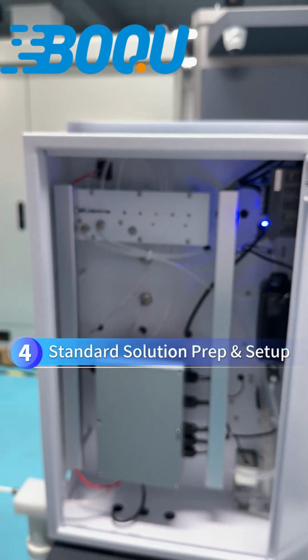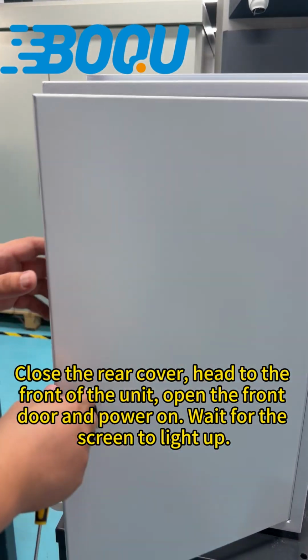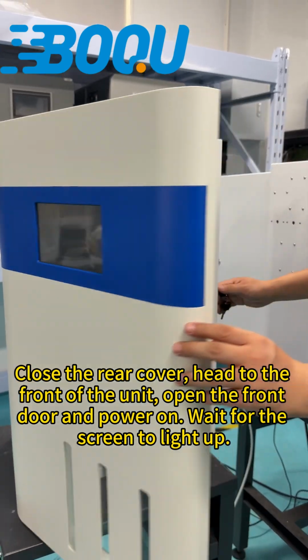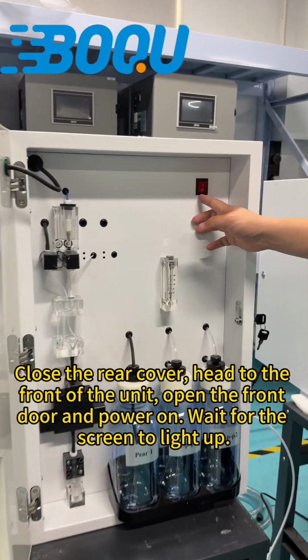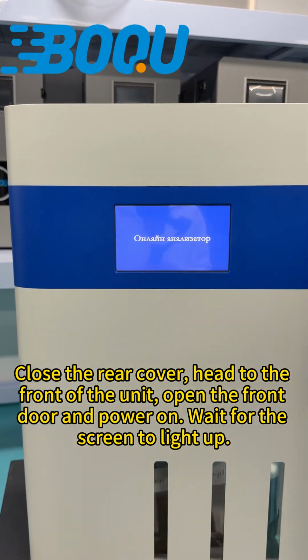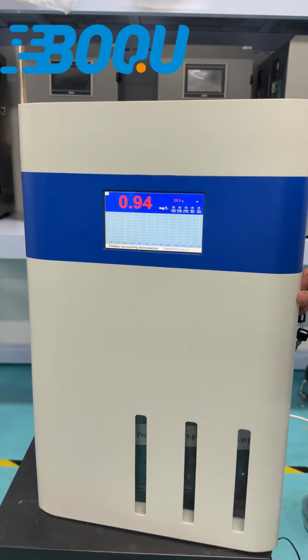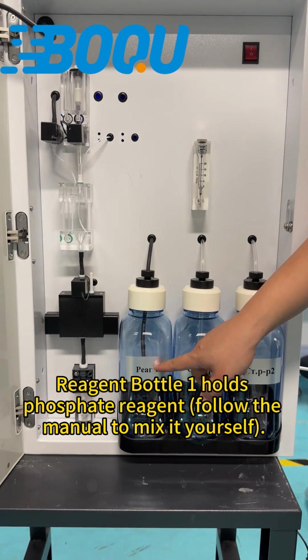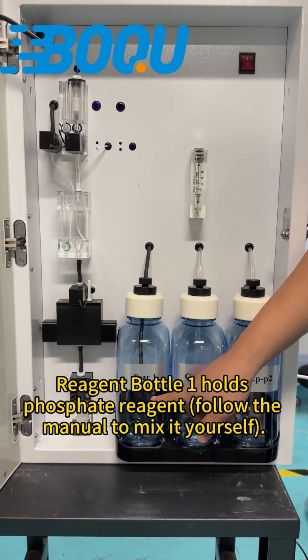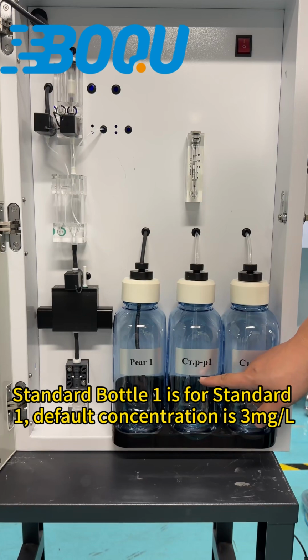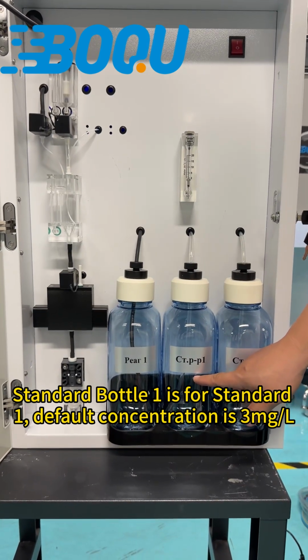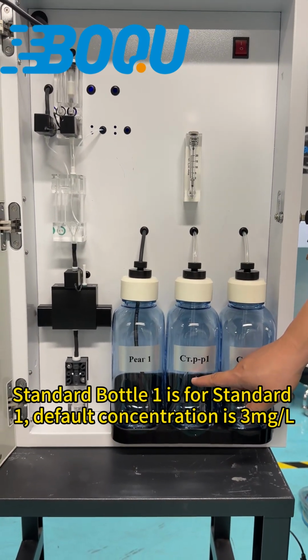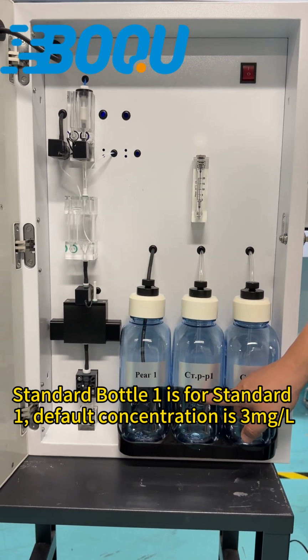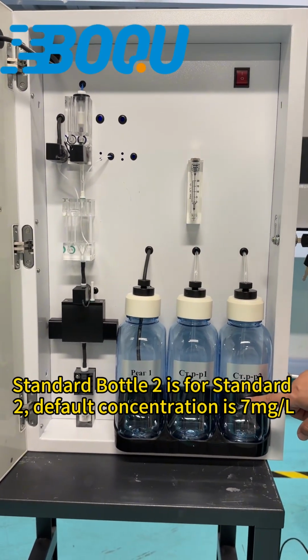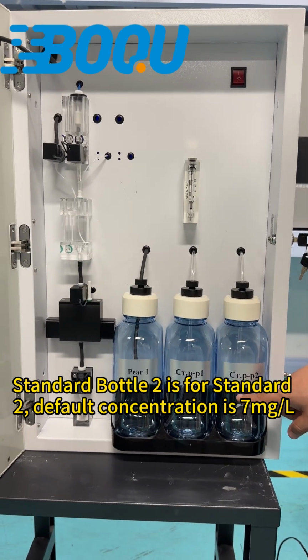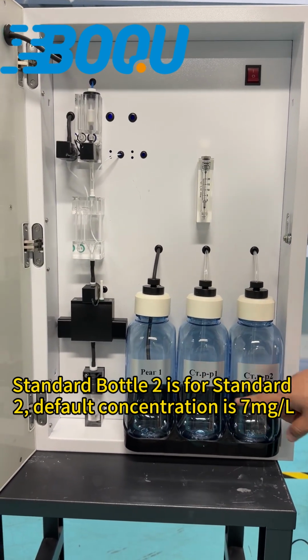Standard solution prep and setup. Close the rear cover. Head to the front of the unit. Open the front door and power on. Wait for the screen to light up. Reagent bottle 1 holds phosphate reagent. Follow the manual to mix it yourself. Standard bottle 1 is for standard 1. Default concentration is 3 mg per liter. Standard bottle 2 is for standard 2. Default concentration is 7 mg per liter.